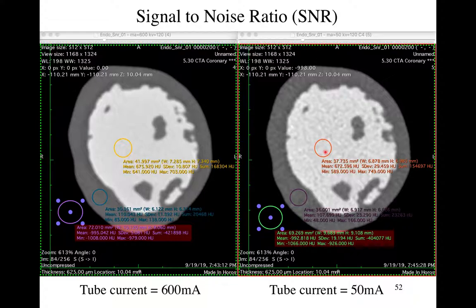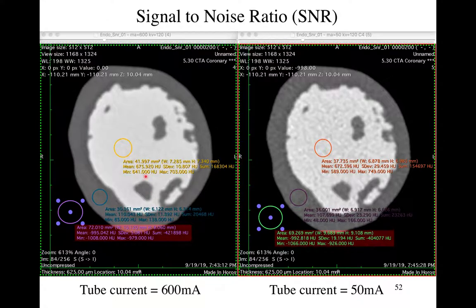So the mean is 672 divided by 29, which gives you the confidence you have in that mean. When we use 12 times as many photons to make the picture, we get a mean of 675 — basically the same — but the standard deviation drops to 10. We get a much more constant value, demonstrating the effect of photon count on noise.